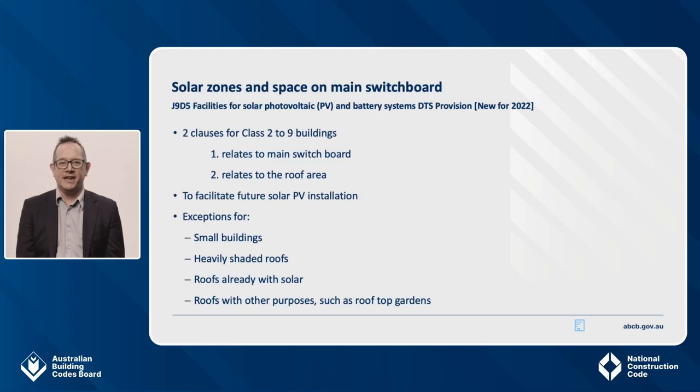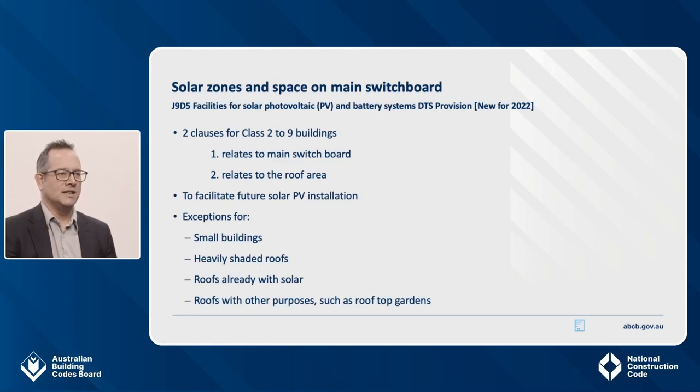We'll now look at the new provisions intended to allow for easy addition of solar PV and batteries to Class 2-9 buildings. This is J9D5, Facilities for Solar Photovoltaic and Battery Systems. There are exceptions for buildings that are small, heavily shaded, already have solar, or where most of the roof is used for other purposes like a roof garden or car parking. There are two clauses in this provision. Clause 1 relates to the building's main switchboard — to facilitate the future installation of solar PV, you are required to leave at least one labelled circuit breaker slot on the main switchboard for future use, and the main switchboard must be sized to accommodate supply from a PV system that covers 20% of the roof space. There's also a requirement to leave at least one circuit breaker slot for a battery storage system. The second clause sets out the requirement to leave 20% of the roof clear for ease of retrofit.